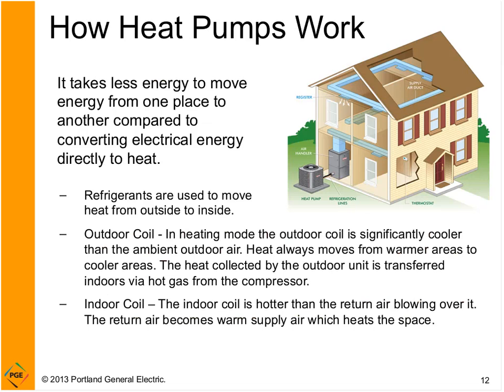How heat pumps work. This is a broad overview of how all heat pumps work. Basically, the concept with a heat pump is it takes less energy to move energy from one place to another compared to converting electrical energy directly to heat. When you have an electric resistance heater, let's say a baseboard, all the electrical energy that goes into the baseboard results in heating energy. With a heat pump, you actually get more energy out of the system, and that's because you're moving heat from the outdoors to the indoors. So that's the big efficiency gain with heat pumps.